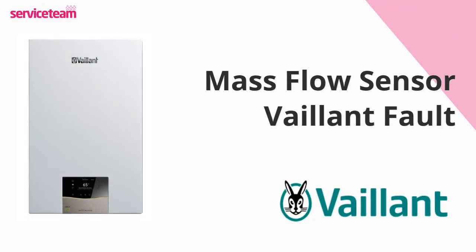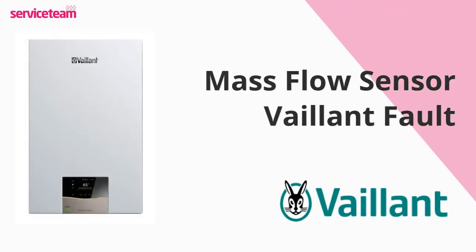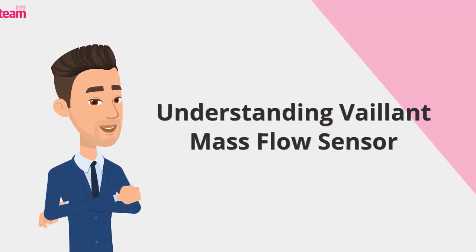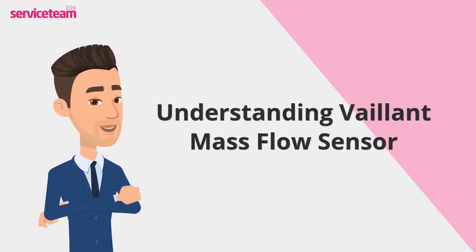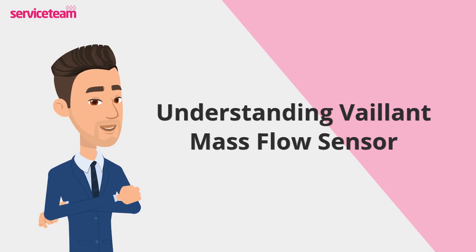Let's figure out how to resolve the mass flow sensor error on the Vaillant boiler. The mass flow sensor is a small but vital component inside your Vaillant Eco-TEC boiler. You usually find it just behind the gas valve, connected to the fan.